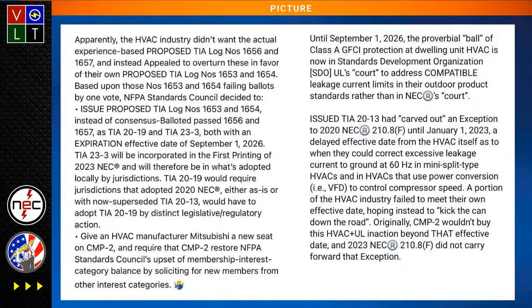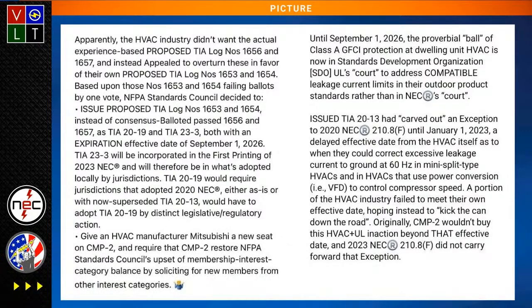The next part talks about the issue, TIA 20-13, which had carved out an exception to 2020 NEC 210.8(F) until January 1st, 2023—a delayed effective date for the HVAC industry to correct excessive leakage current to ground at 60 hertz in mini-split type HVAC, and HVACs that use power conversion or variable frequency drive to control compressor speed. It says a portion of the HVAC industry failed to meet their own effective date, hoping instead to kick the can down the road. First of all, there's no kicking the can down the road.